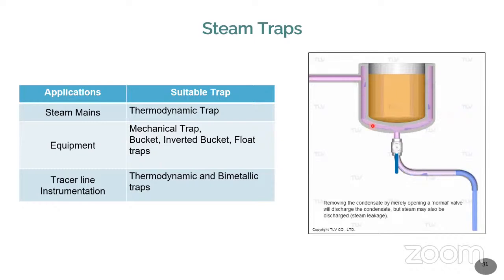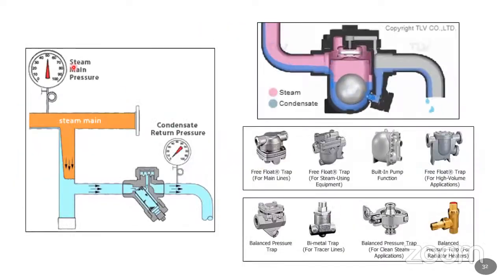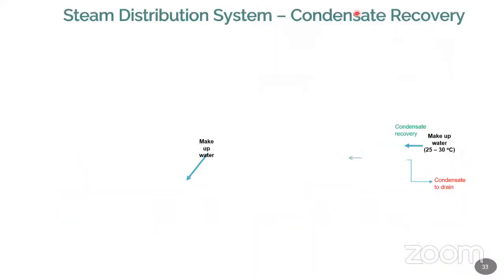So when the steam starts to condense, the water will go out like this. Then this is the steam in the main pipe and the floating trap valves, different types of floating valves. So you can see the steam traps. Normally a small downward slope of pipe will always be provided in the main line. So if the water comes out in the main line, it will go like this, and when the level is higher, the valve starts to open, and the condensate comes out from the system.